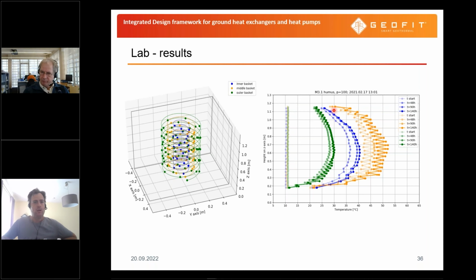Of course, right on the heating cable, we have the hottest temperatures. So the temperature is plotted on the x-axis here, and the Z coordinate on the y-axis. Of course, the hottest temperatures are on the cable itself. Then we have the blue one that is in the center. Of course, it's not as hot as on the cable itself, but it also has some storage effect here, and of course less heat losses than the basket on the outer side. That is the green curve. So this is what we get out of our measurements.